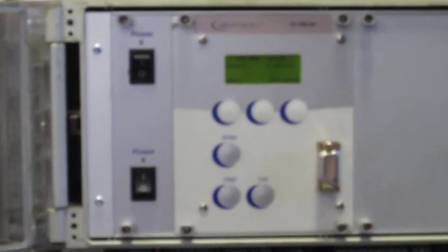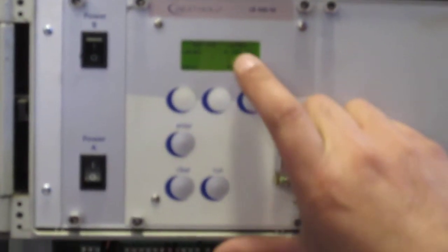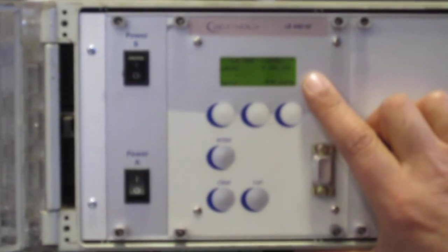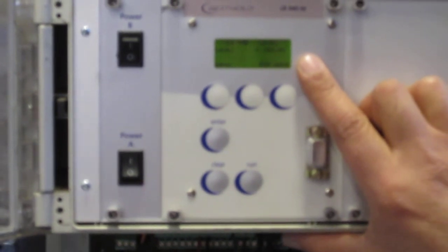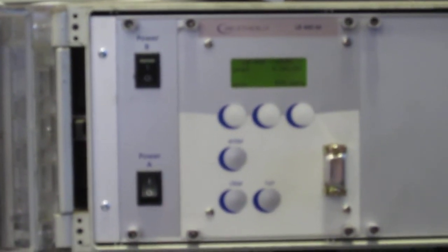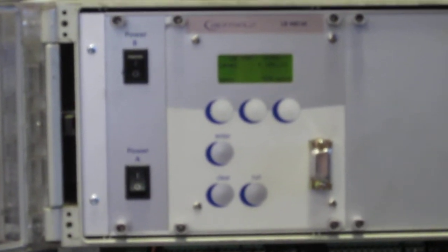At this point, I can go around to live data, or I can just say run, and it's automatically going to start running and measuring. Run is also measuring my calibration. So here I'm reading right now, this is a mock calibration, we didn't really do my counts, but I got 101.3%. And we didn't do the time constant long enough, but pretty much that's how you calibrate, how you run the gauge.